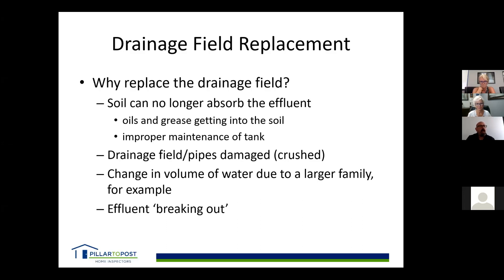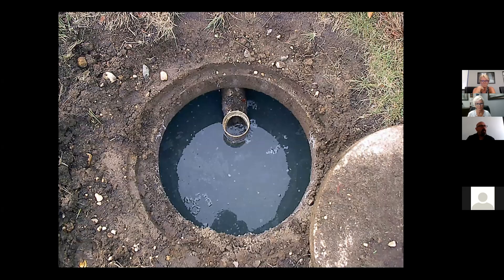Looking at the top of the tank — this one is fairly clean. You can see the baffle here; water comes in and this is open in case of too much water. The level in the tank should remain consistent. If you're seeing the level go full, then two inches lower, then full again, it indicates either large quantities being dumped in quickly — which is bad — or the system is starting to plug out.